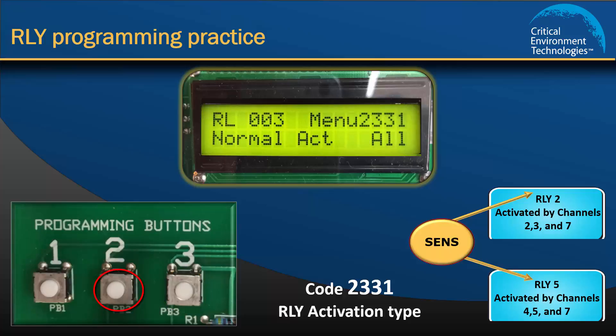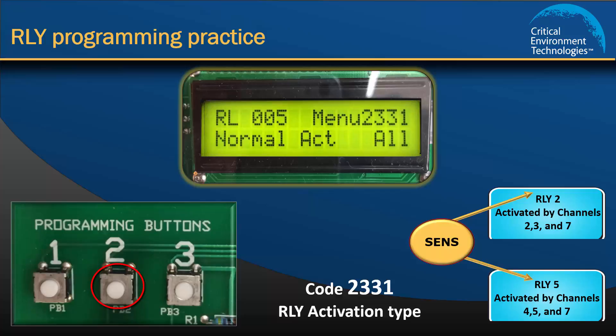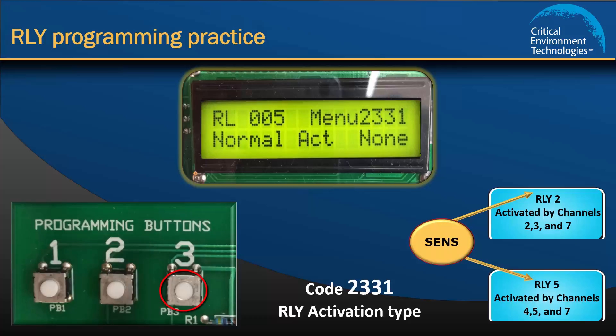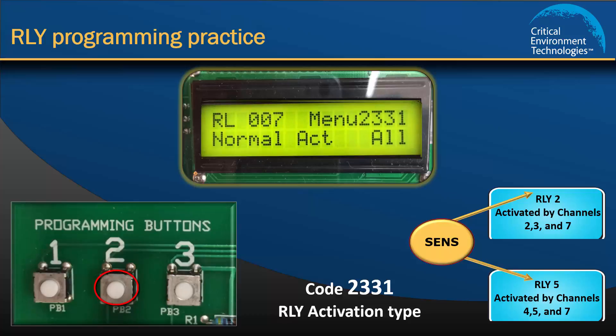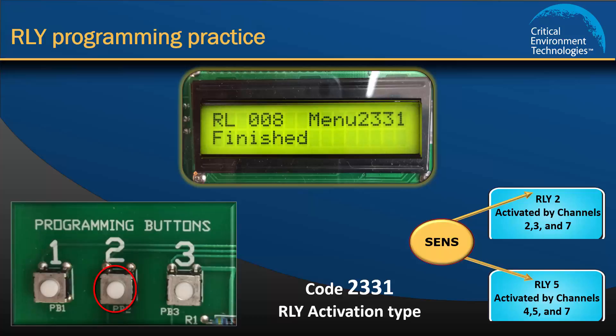We are not concerned with Relay 3, so press 2 again to continue to Relay 4 and again to continue to Relay 5. For Relay 5, we want to assign activation type Sens. Just like before, press programming button 3 once to scroll to None and then again to scroll to Sens. To save your selection, press programming button 2 consecutively to move on to Relays 6, 7, and 8. When you reach the last relay, press 2 again to finish and exit the menu. The screen will display "Finished" and then return to normal operation.